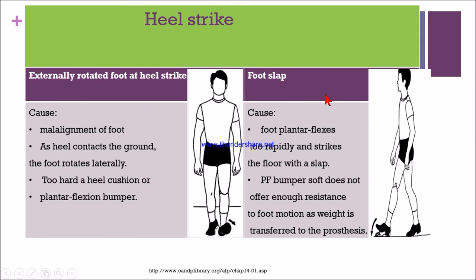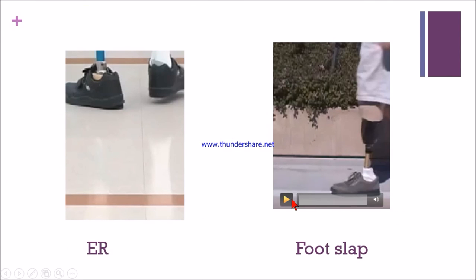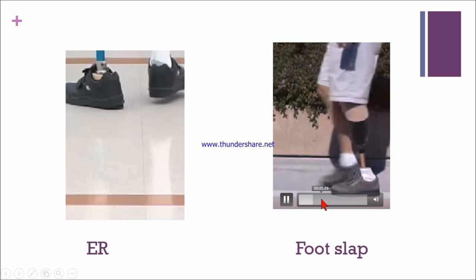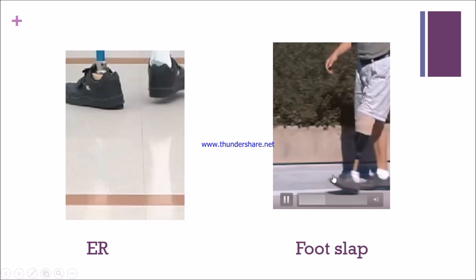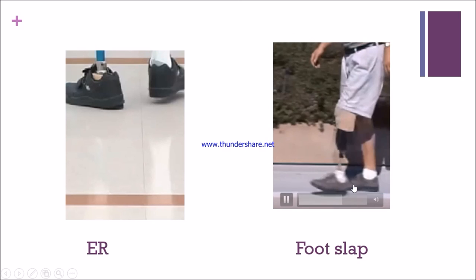Foot slap at heel strike occurs when the foot plantar flexes too rapidly and strikes the floor with an audible slap sound. This happens when the plantar flexion bumper is too soft and does not offer enough resistance, so the weight of the foot is transferred rapidly to the prosthesis. In this video, we can see the foot slapping repeatedly because the plantar flexor bumper is too soft.